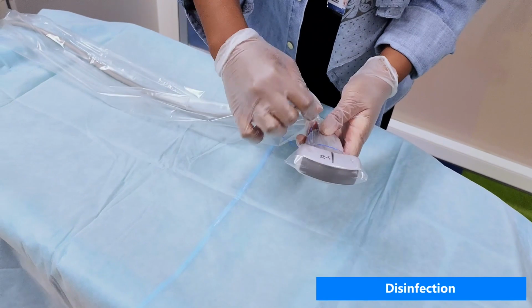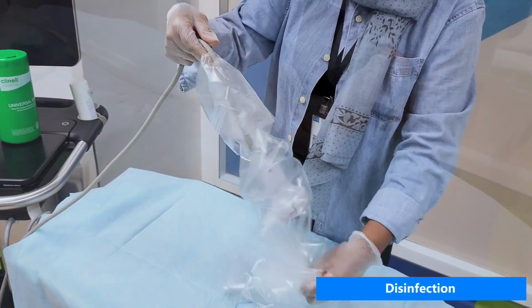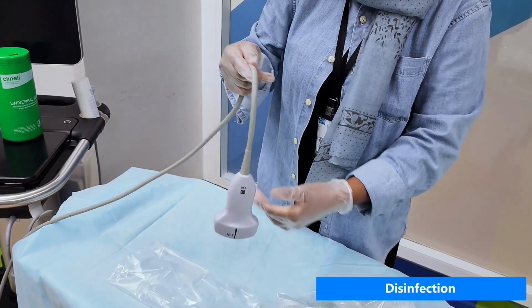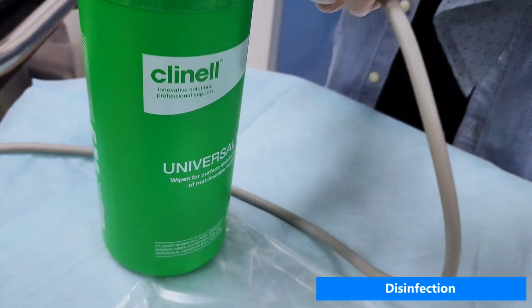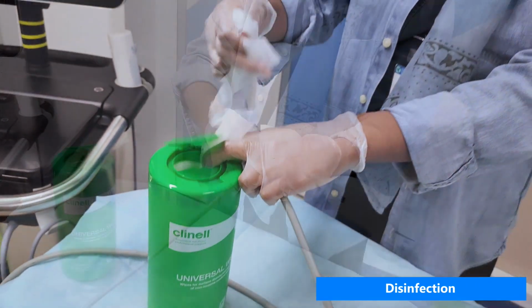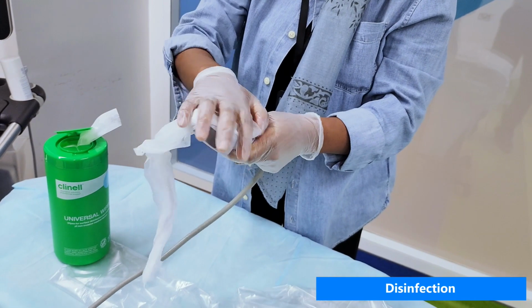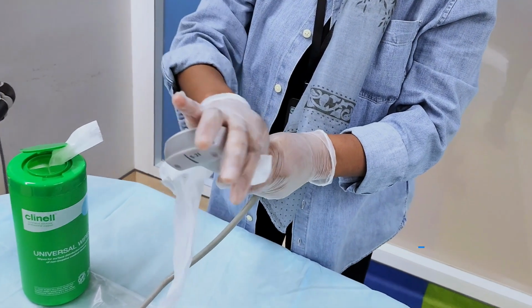In terms of cleaning and disinfection, the recommendation from the machine manufacturer is that everything be cleaned down and wiped with flannel or Clinell wipes that do not contain alcohol, to prevent damage to the transducers, cables, and the machine itself.